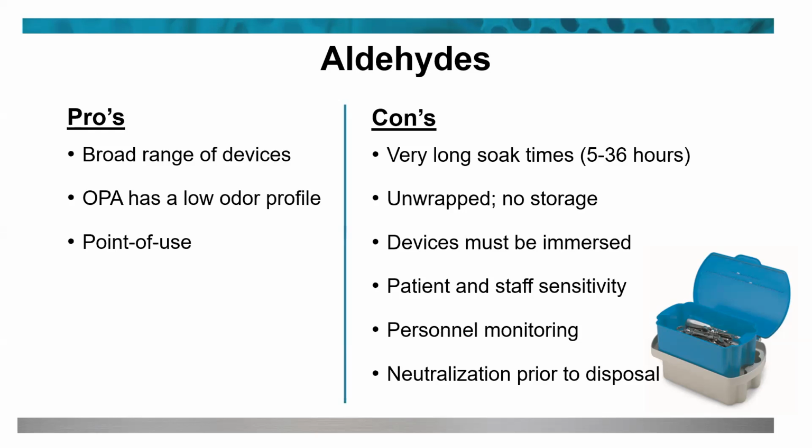Some patients and staff do have sensitivity to aldehydes. I know that some people who have colonoscopies can develop a sensitivity to the aldehydes. There is no personal monitoring with this. With EO, you had to wear the badges; there isn't any kind of personal monitoring with this. And you have to neutralize these when you're getting ready to dispose of them so they're safe for the environment.